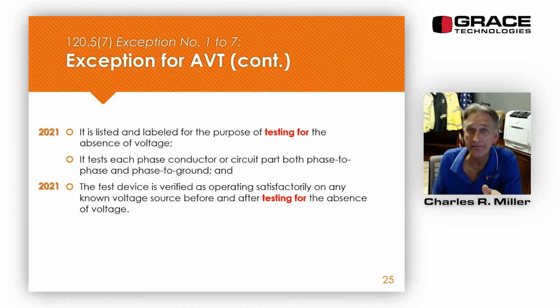It has to do everything we would have to do if we're in front of the equipment, meaning that it has to test itself on any known voltage source. It has to test phase to phase and phase to ground. Then it has to test itself on any known voltage source.